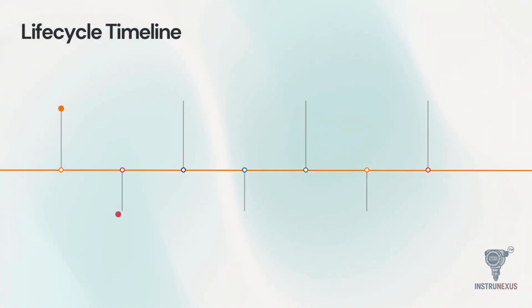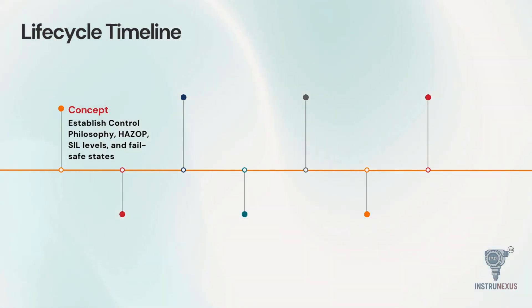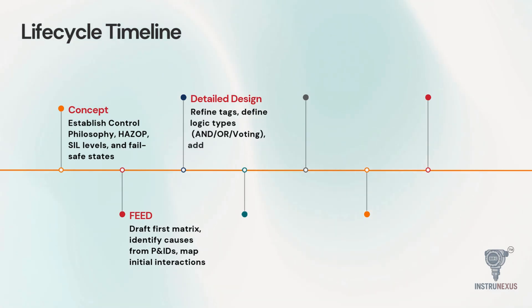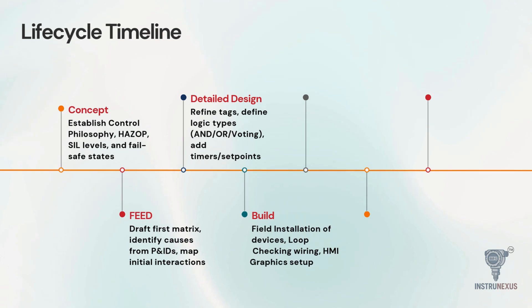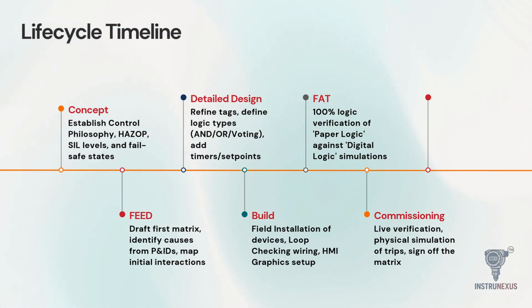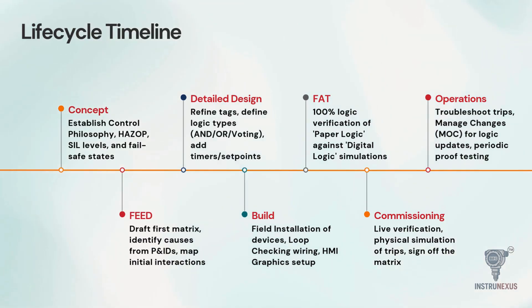To understand the matrix, we have to look at its timeline. It is not a static document — it evolves. It begins in the concept phase, where we establish the control philosophy and safety levels. It moves to front-end engineering design, or FEED, where the first draft is created based on P&IDs. In detailed design, we refine the tags and add logic timers. During the build phase, physical installation and loop checking occur. Then comes the FAT, where we verify the logic digitally. We then move to commissioning for live verification. Finally, in operations, the matrix is used for troubleshooting and managed through strict management of change procedures.